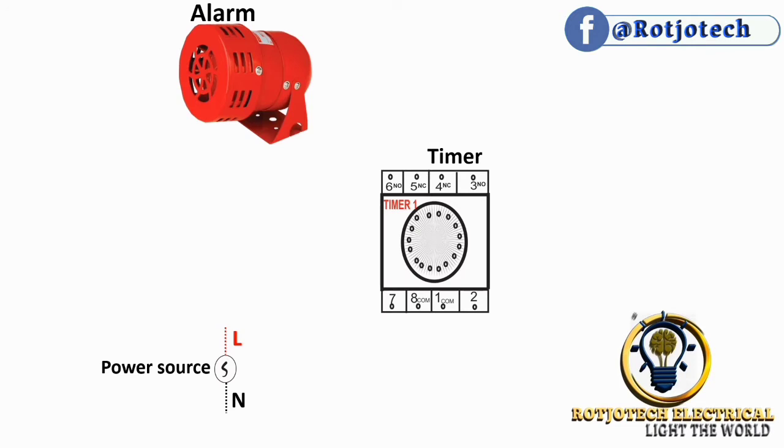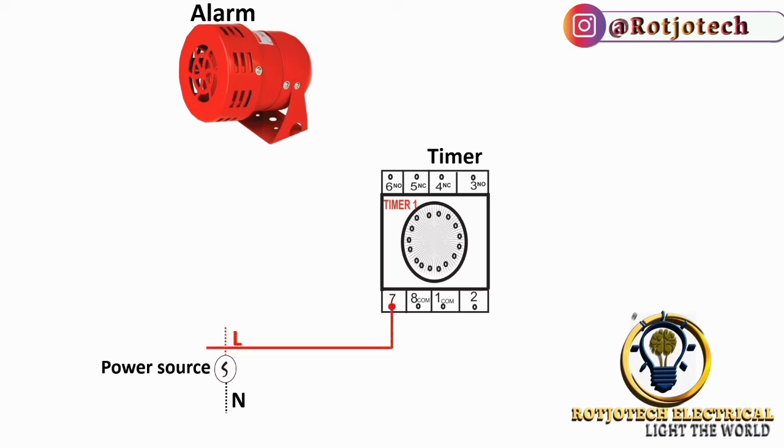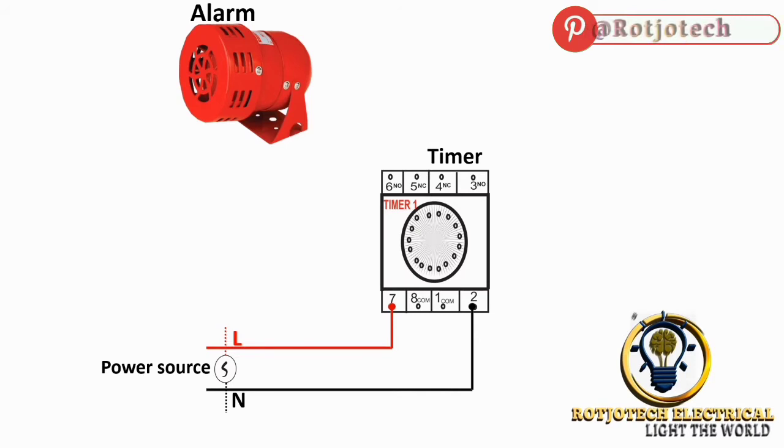Okay, let's start the connection. First, we are going to connect the live to terminal number 7. And after that, we are going to connect neutral to terminal number 2. As we have powered terminal number 7 and terminal number 2, that means we have powered our timer. This timer can energize.